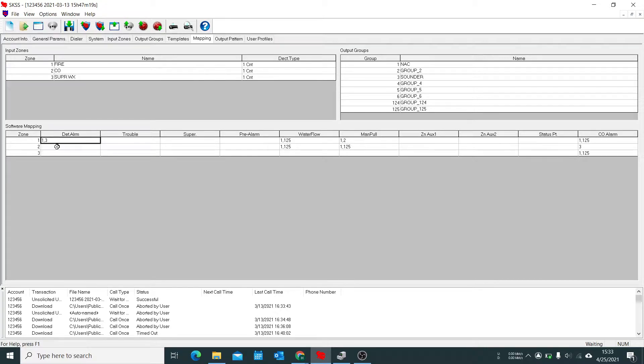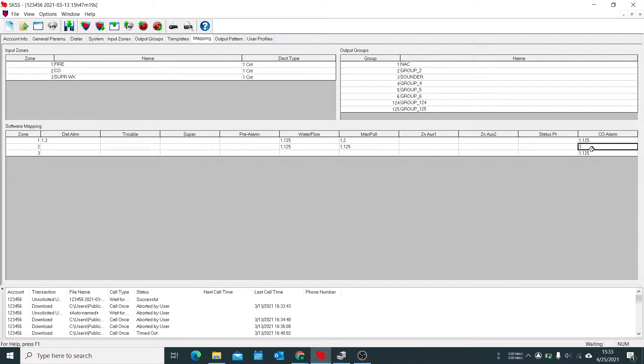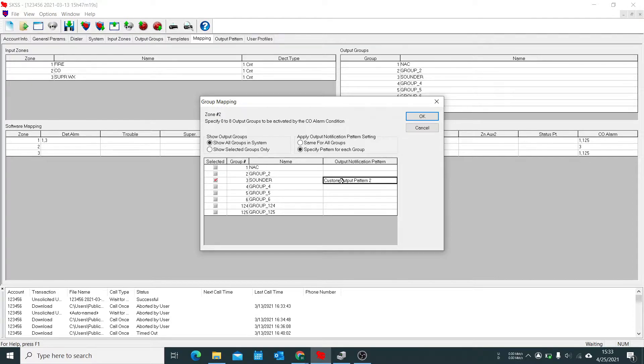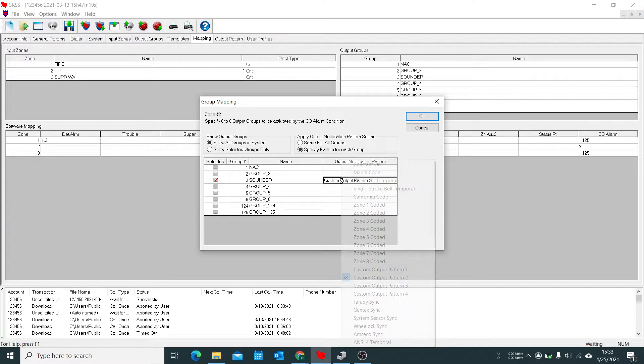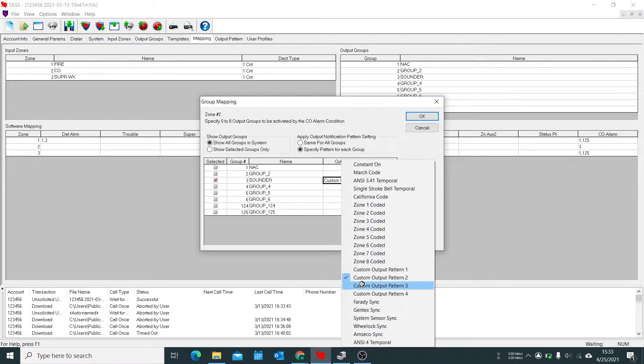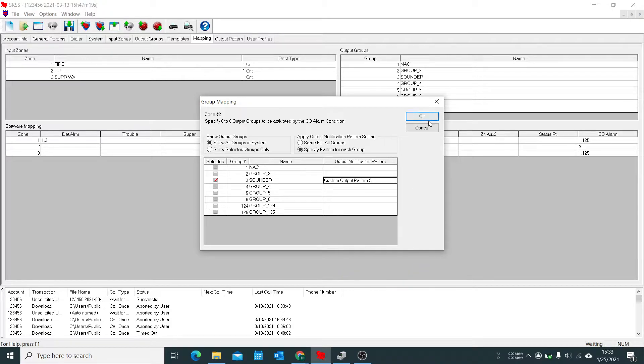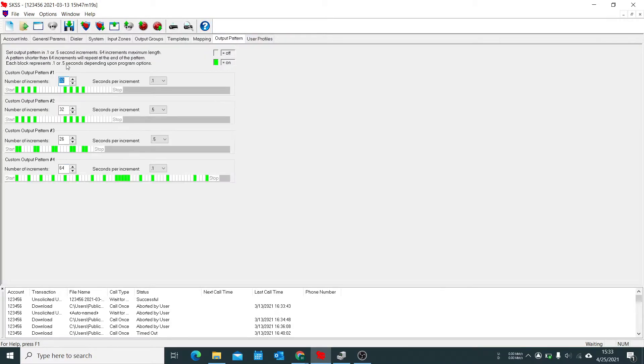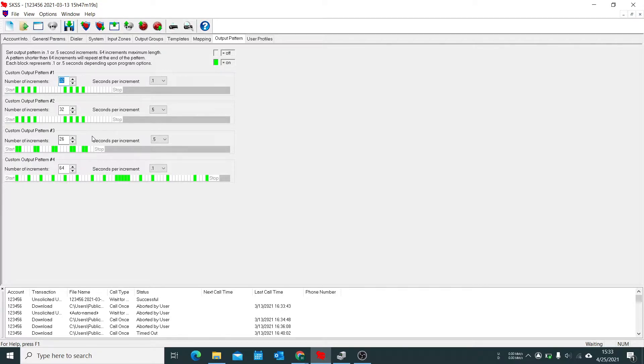Now for zone two which is a contact input which is CO, we can leave this stuff blank for now but we also want this set to be zone two to be output three as well. But we also want that to be a different pattern. So we're going to select custom output pattern number two. And if we go to our output patterns we see number two is code four which is standard for CO detectors.